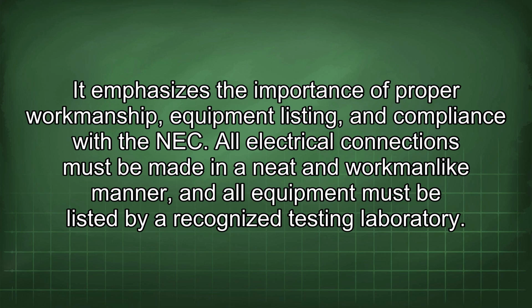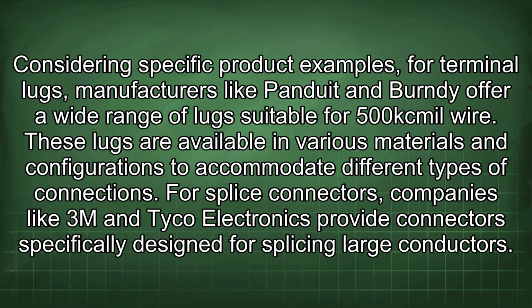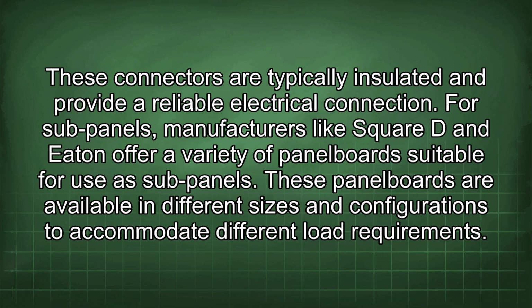recognized testing laboratory. Considering specific product examples, for terminal lugs, manufacturers like Panduit and Burndy offer a wide range of lugs suitable for 500 kcmil wire. These lugs are available in various materials and configurations to accommodate different types of connections. For splice connectors, companies like 3M and Tyco Electronics provide connectors specifically designed for splicing large conductors. These connectors are typically insulated and provide a reliable electrical connection.